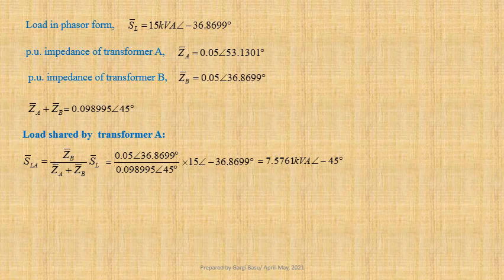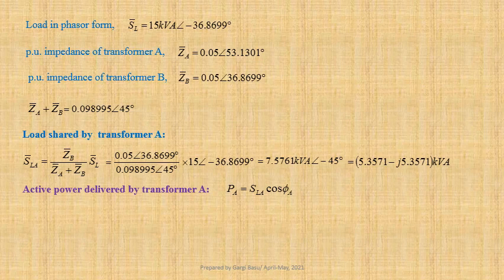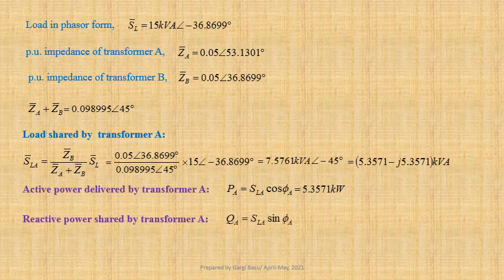This may be written in Cartesian form as 5.3571 minus j 5.3571 kilovolt ampere. Active power delivered by transformer A, PA equals SLA cos phi A, that is equal to 5.3571 kilowatt. Reactive power shared by transformer A, QA equals SLA sin phi A, that is equal to 5.3571 kilovolt ampere reactive. Let us now determine operating power factor of transformer A. Cos phi A equals cos of 45 degree, that is equal to 0.7071 lagging.